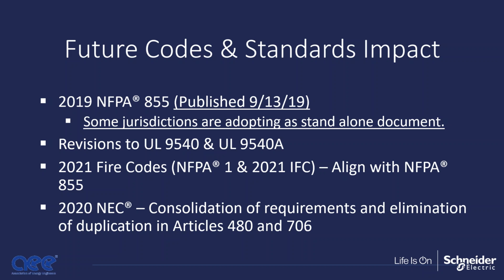We've talked a little bit more about the fire codes, but the actual 2021 fire codes, moving from 2018, are looking to align with some of the requirements within NFPA 855. And then, of course, I mentioned the 2020 National Electric Code. That was a consolidation of requirements and an elimination of duplication in Articles 480 and 706, creating a better differential and line between just batteries and battery installations and actual energy storage systems, which, even if they use batteries, is part of a system, not just the batteries themselves.